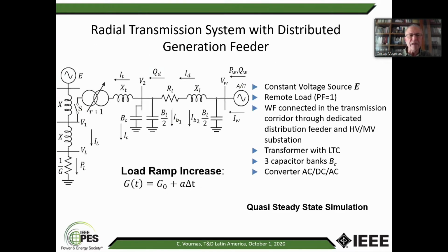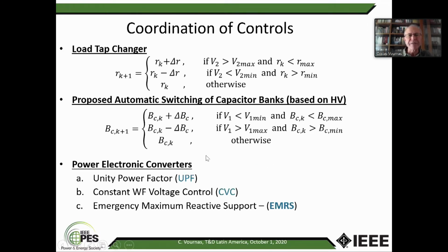Now, you also saw that we have this capacitor bank. This is a variable bank. And as I said, we have usually 3 steps. So in order to coordinate the controls, because the tap changer is controlling the voltage on the secondary, on the distribution side, we decided to make the capacitor banks switch on or off based not on the distribution voltage, but on the transmission voltage. So for instance, if the voltage in the transmission drops below a minimum value, typically something like 95%, so if I have low voltage in the transmission, I switch one capacitor bank.